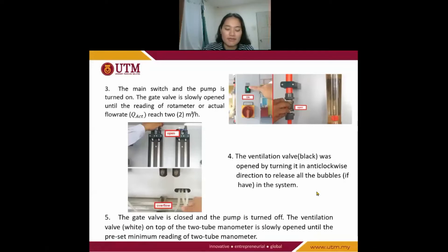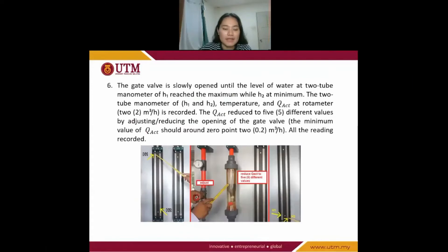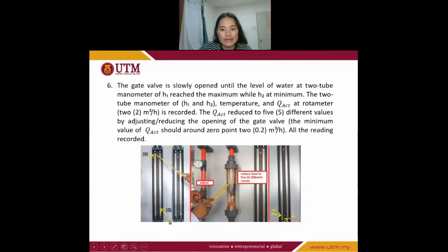Next, the gate valve is closed and the pump is turned off. The ventilation valve — the white one on top of the two-tube manometer — is slowly opened until the preset minimum reading of the two-tube manometer is reached. Next, the gate valve is slowly opened until the level of water at the two-tube manometer H1 reaches the maximum while H2 reaches its minimum.